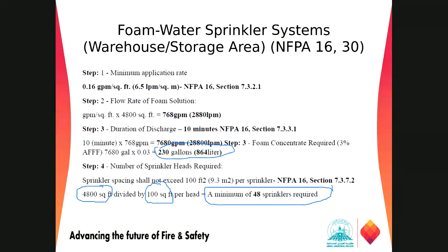And the duration of discharge is 10 minutes, right? We have the discharge duration of 10 minutes. If you multiply all those, for 10 minutes of continuous discharge we need around 7,680 gallons of the foam solution for this one.